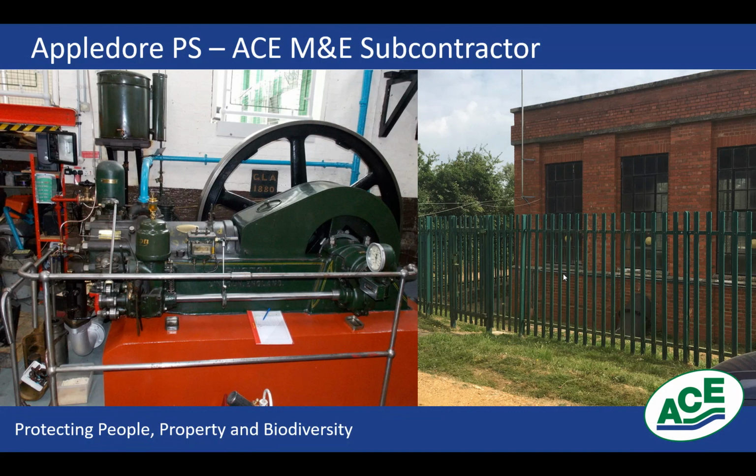So it's an end suction pump. What that means is that the impeller, rather than being underwater, is inside the building and linked to this motor. So first you have to create a vacuum, draw all the air out of the pipework before you turn the pumps on and get the impeller operating. And the benefit of that system is you need a very shallow sump. You don't need much depth in there at all, which of course saves you from digging a large amount of earthworks.